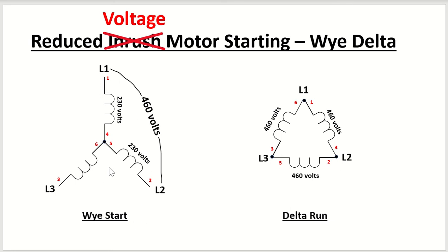This would be a typical 6-lead motor. Now this would not be a dual voltage motor. I'll get to that at the end, how you would do what's called a 12-lead Y delta motor that would be dual voltage. This is a single voltage motor, has leads 1 and 4, 2 and 5, 3 and 6, and like most Y connected motors, you would just go around clockwise 1, 2, 3, and then 4, 5, 6. When you switch it to the delta configuration, you're taking this winding here, 1 and 4, here's your 2 and 5, here's your 3 and 6, and you're connecting it in the delta configuration.